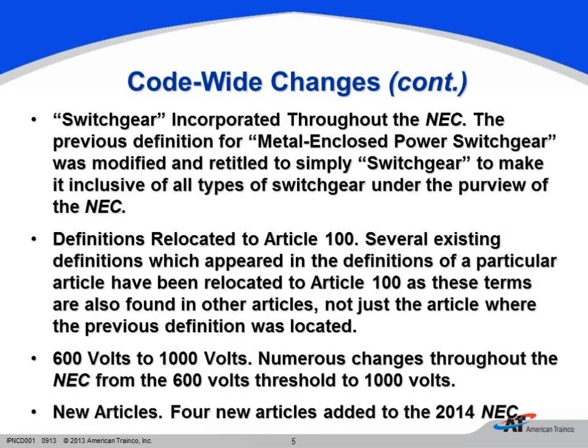In Article 100, we'll see that there has been a lot of definitions relocated. For familiar users of the code book, you would notice that in the left-hand margin, there is normally a bullet when we would see a deletion. So one of the ones that we might see, if we went to Article 430, we would see a bullet in 430.2. Dot 2 is, of course, definitions pertaining just to motor circuits. And one of those definitions that were deleted actually got relocated into Article 100, and they changed the title of it a little bit. It was motor control circuit, and now it has only been defined as control circuit.